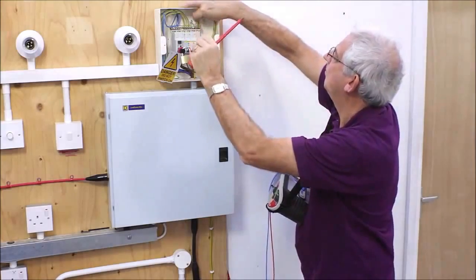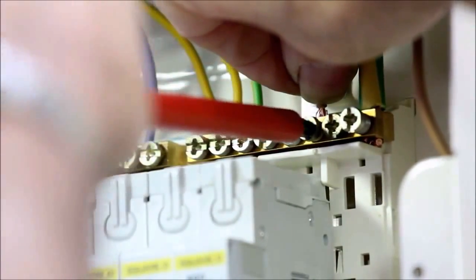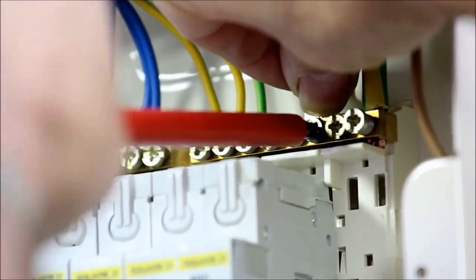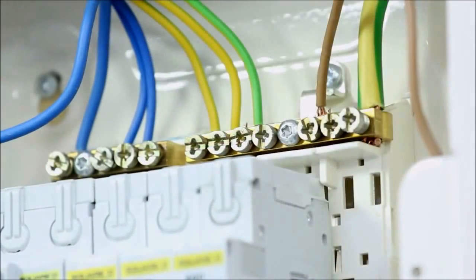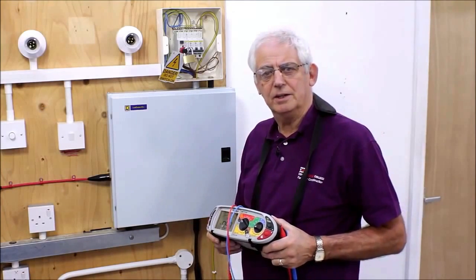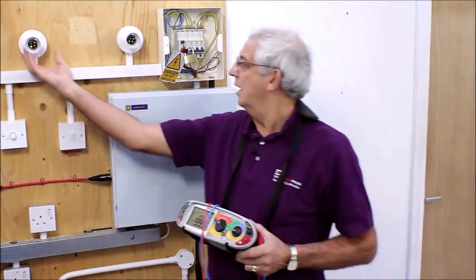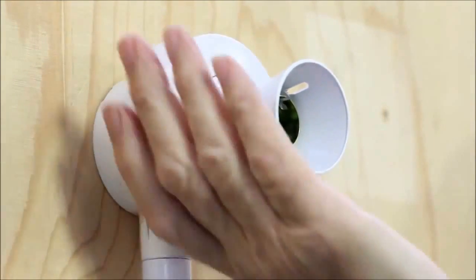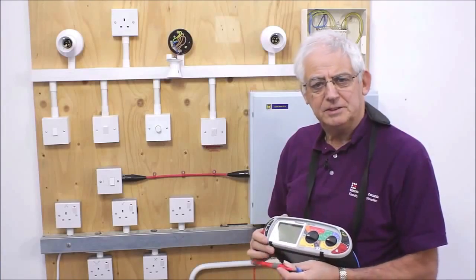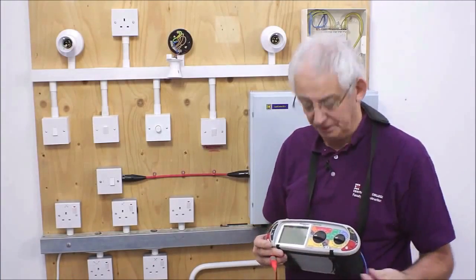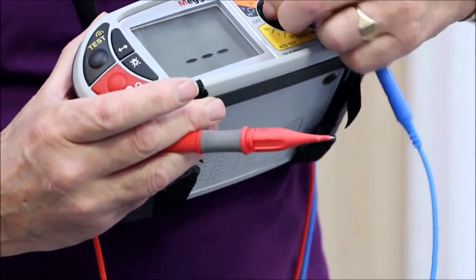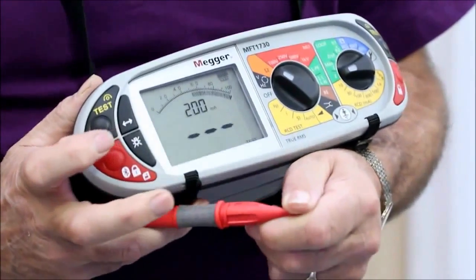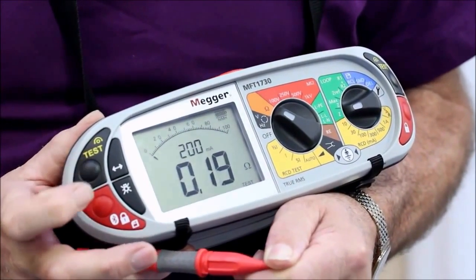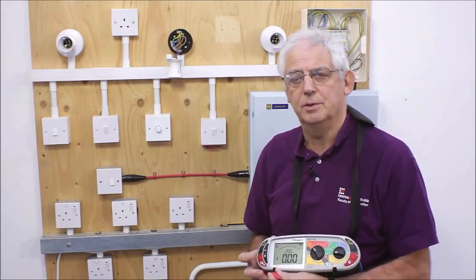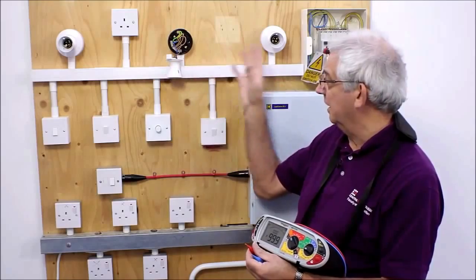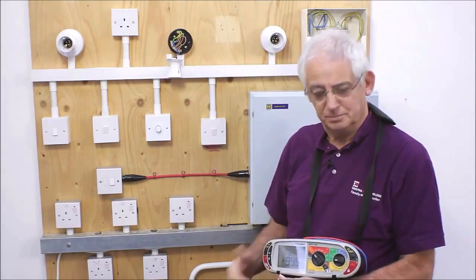Okay, I need to get a nice tight connection on this because I don't want a high resistance joint, which will result in us having a very false reading. Okay, so I now need to go to the light point that I'm going to work on. If I just take it apart for a second, I don't need to disconnect anything. I now need to make sure that my meter is going to be reading accurately, so I need to zero the leads. First of all, I set it to ohms, hold the ends together nice and firmly, wait until I get a reading, push the zero button, and the leads are now zeroed. So when I take a resistance value, I'm actually just going to get the resistance of the cables rather than the resistance of these leads as well.